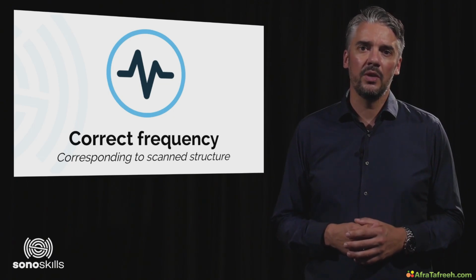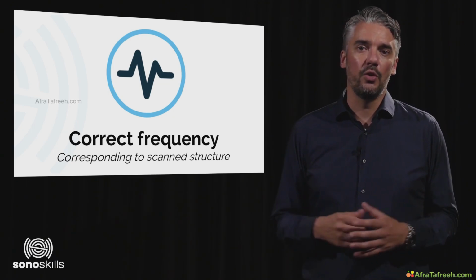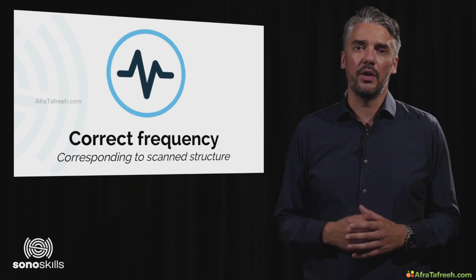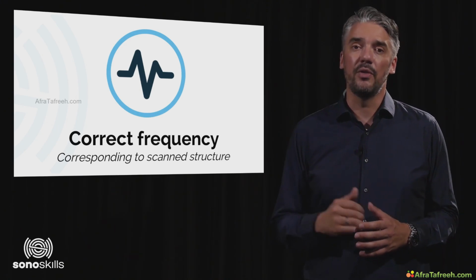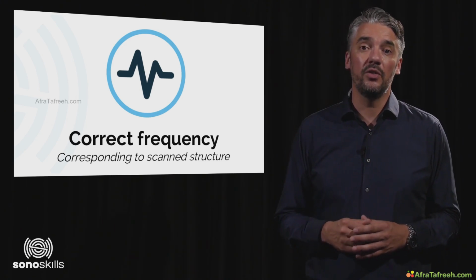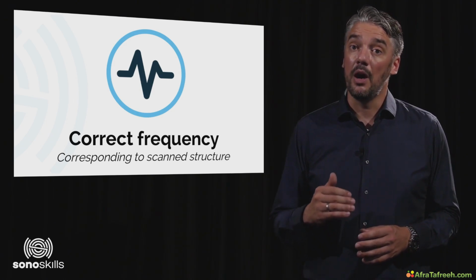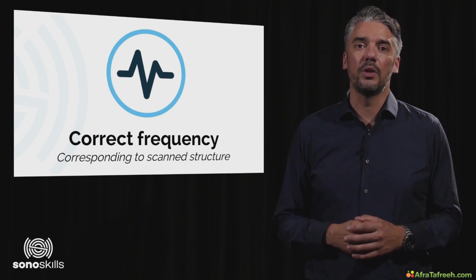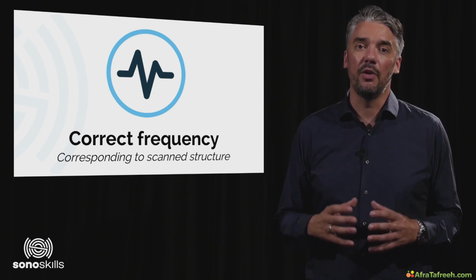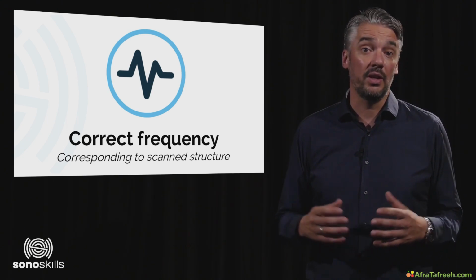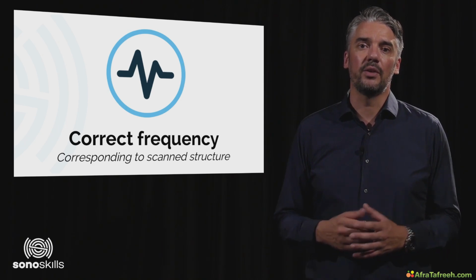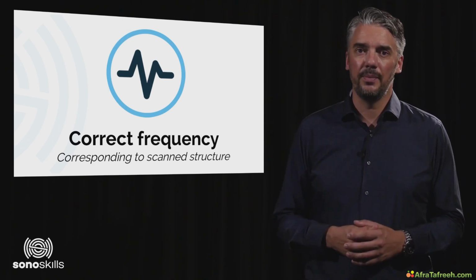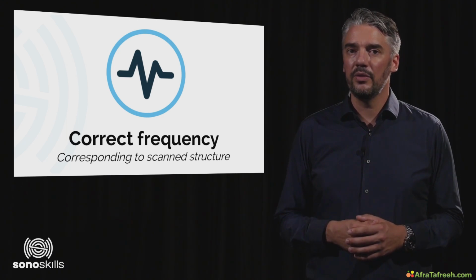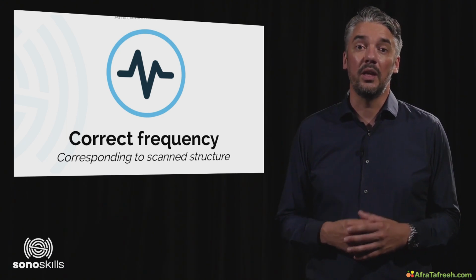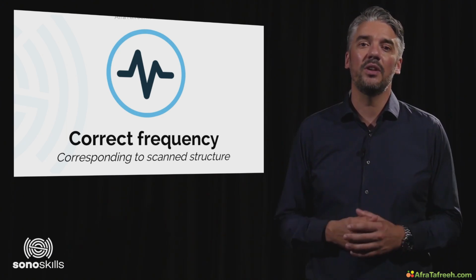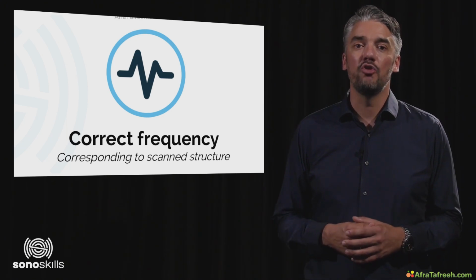Higher frequencies are used for the resolution of more superficial structures, and lower frequencies are used for better tissue penetration. There are no hard and fast rules regarding the precise frequency for each specific depth, as it can vary due to a number of factors, including tissue thickness. A general rule is that the highest frequency that provides adequate tissue penetration and visualization should be utilized.